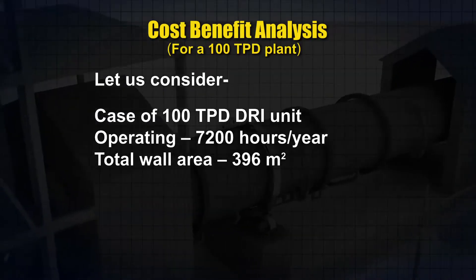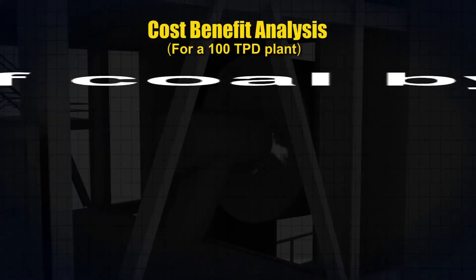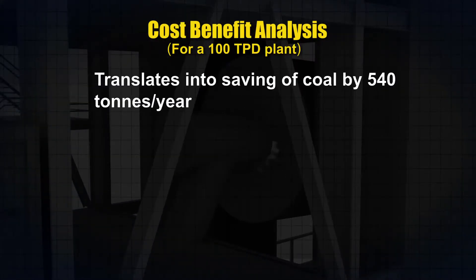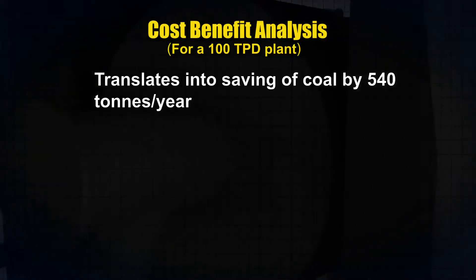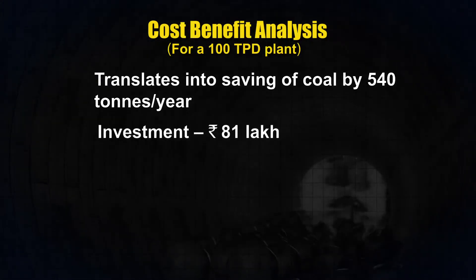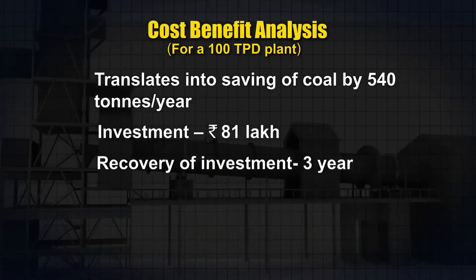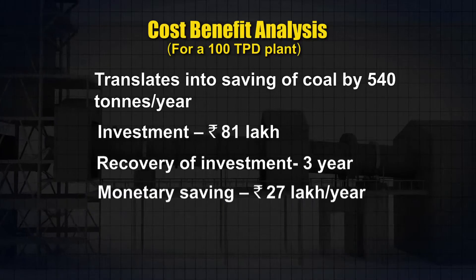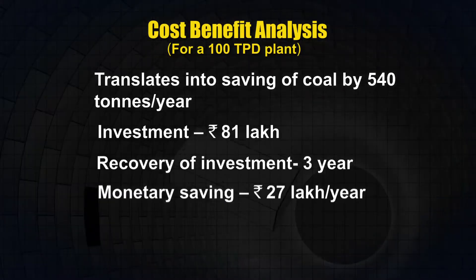The total wall area is 396 square meters. The replacement of conventional refractory with mullite based refractory can lead to a saving of 540 tons of coal per year. Thus, an investment of 81 lakh rupees can be recouped within a period of 3 years, with a monetary saving of 27 lakh rupees per year.